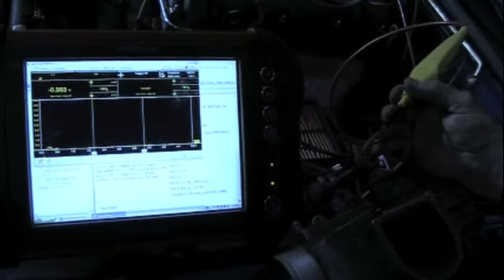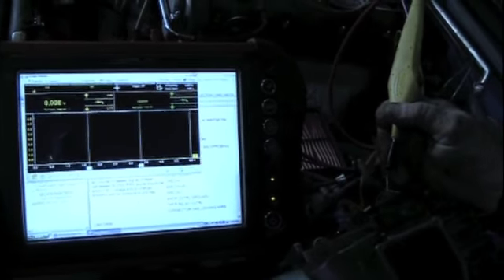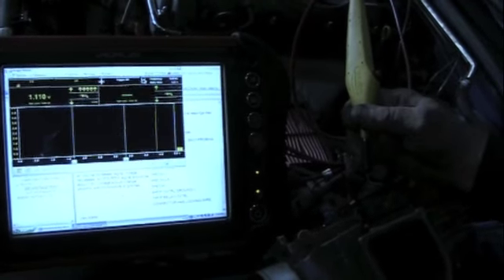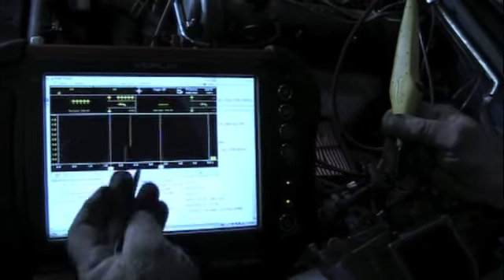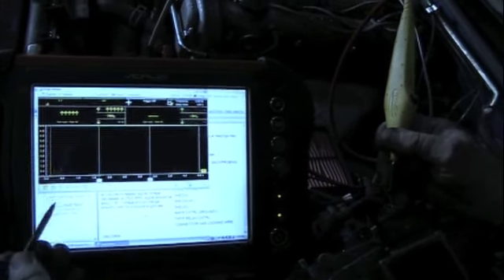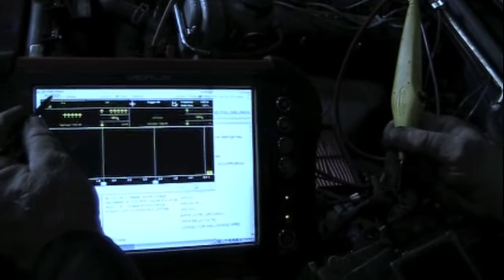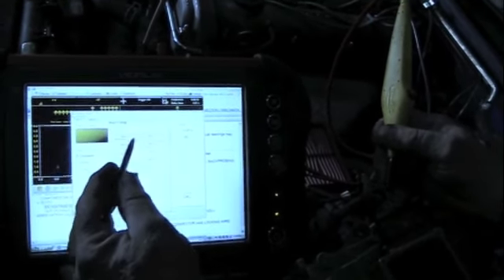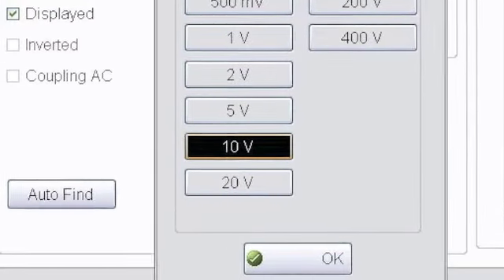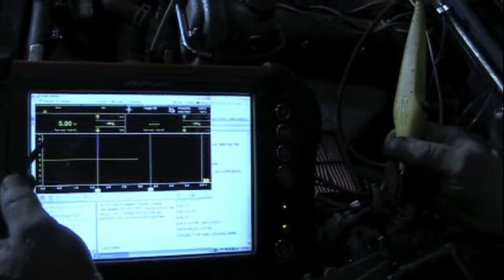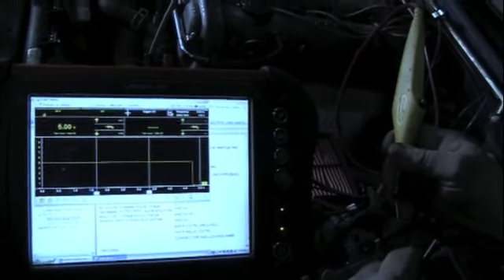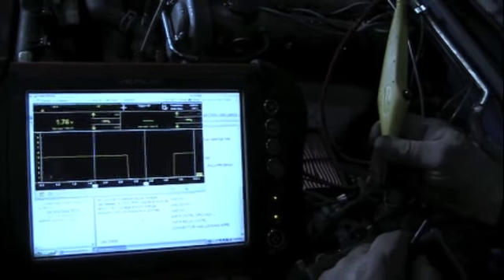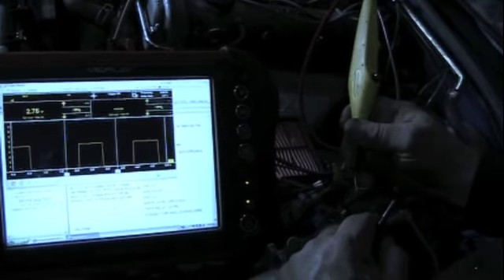So I want to back probe my 5-volt reference, which is wire number 4. I put that in there, back probe it. See my scope go up. It's actually not showing. I want to see that better. So I'm going to change my trace from 5-volt to 10-volt. And now I can see my 5-volt reading. When I take this away, it goes down. So I've got a good 5-volt reference.